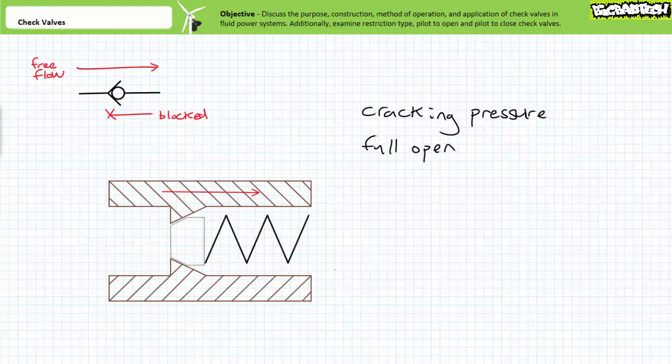Consider, however, a check valve with an extremely heavy bias spring employed as an especially primitive pressure relief valve. For example, consider a check valve with a heavy bias spring and a cracking pressure of 700 psi and a full open pressure of 800 psi.